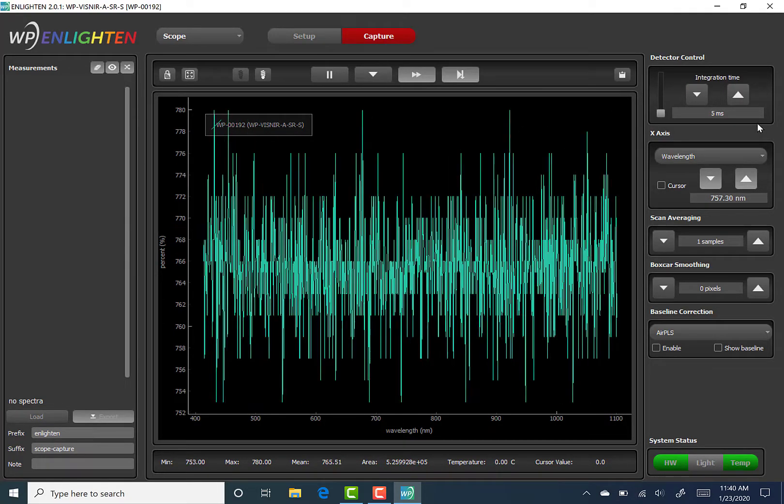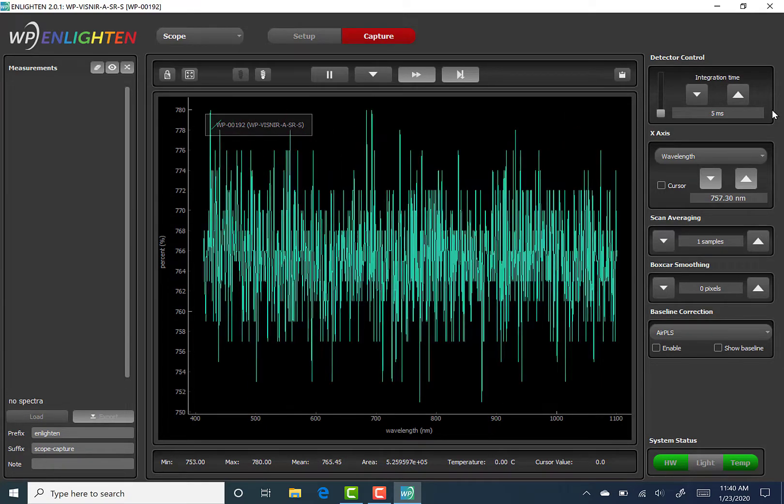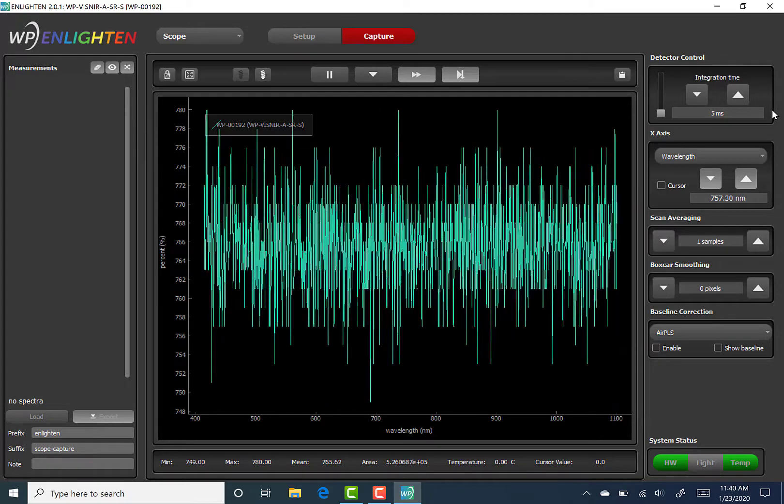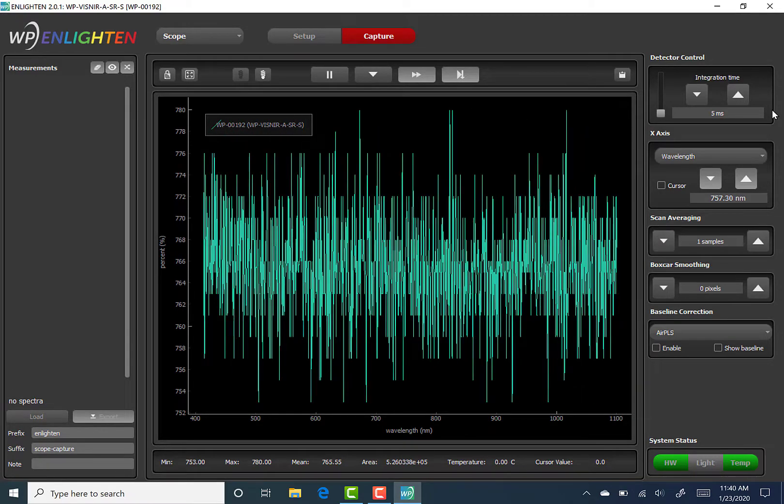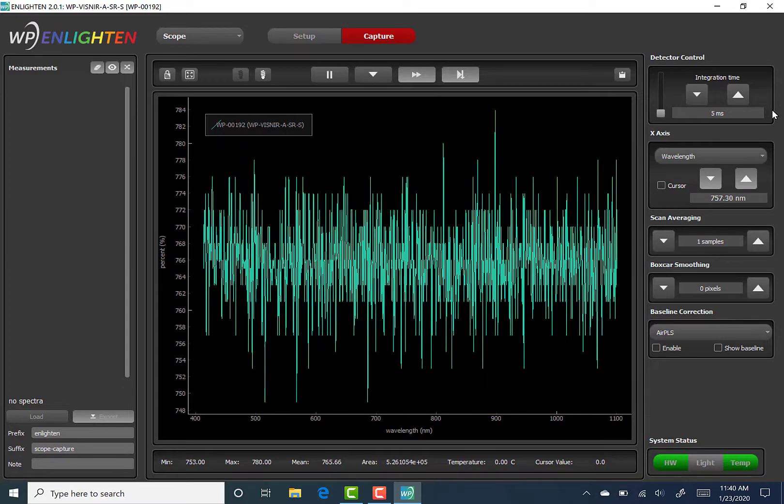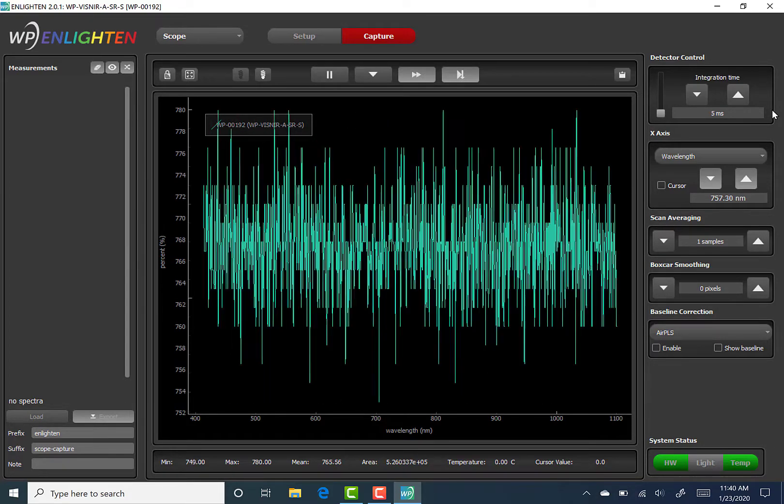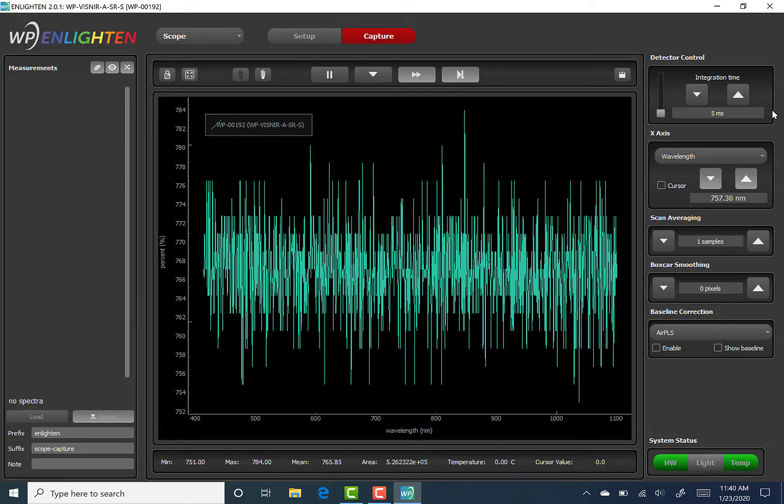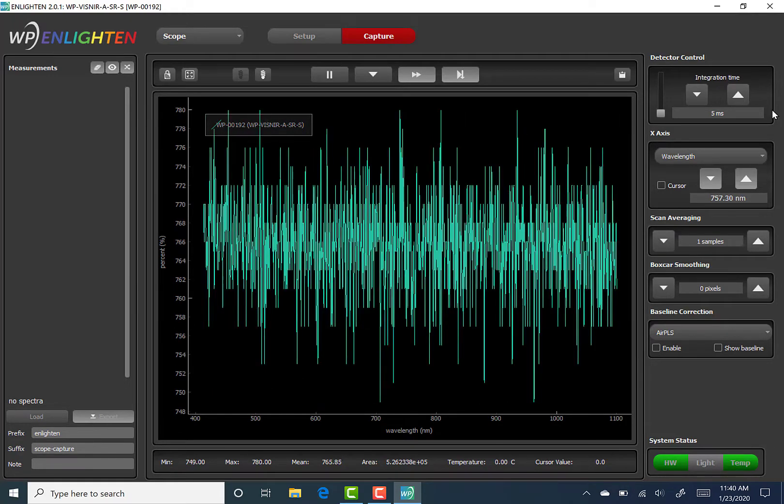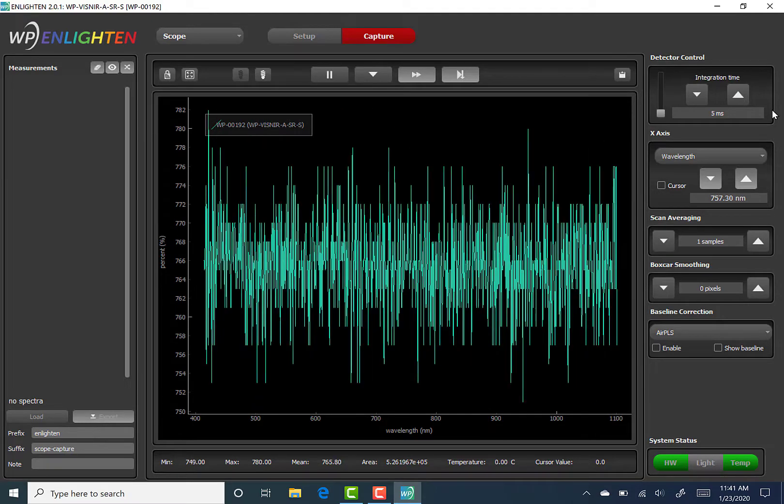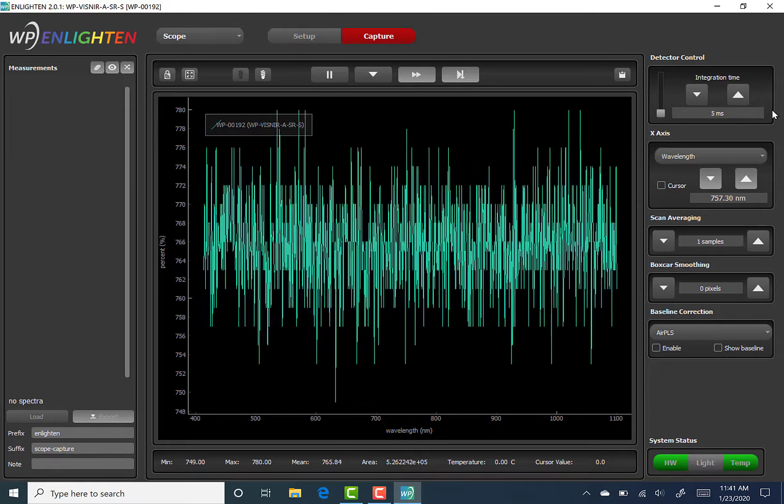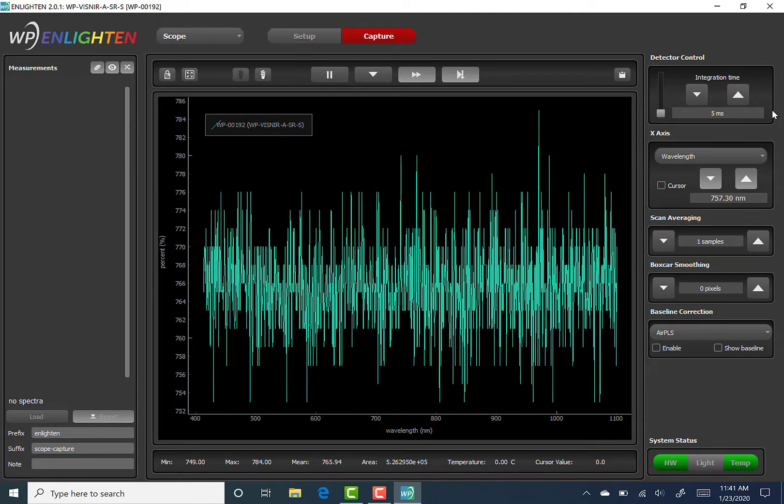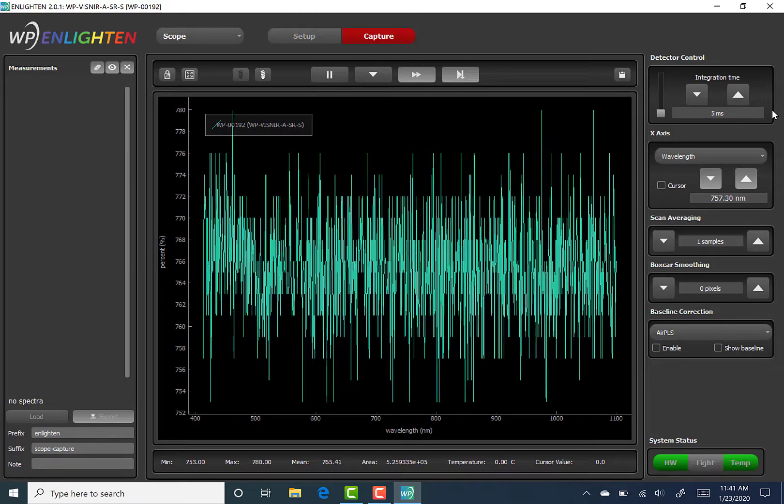Detector integration time is the amount of time that the detector is able to capture the incoming light from a measurement, so longer integration times will help detect extremely faint spectroscopic phenomena, such as Raman-Stokes scattering and fluorescence/luminescence emission, but also may increase noise and baseline effects by allowing more time for electrical readout noise and ambient light to accumulate. However, the user may want to decrease integration time if too much light is captured by the detector. It is the user's responsibility to determine the optimal integration time and experimental setup.